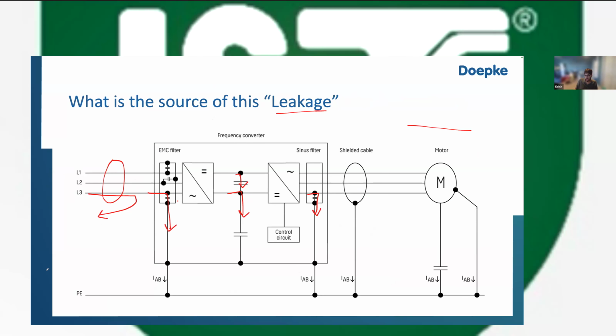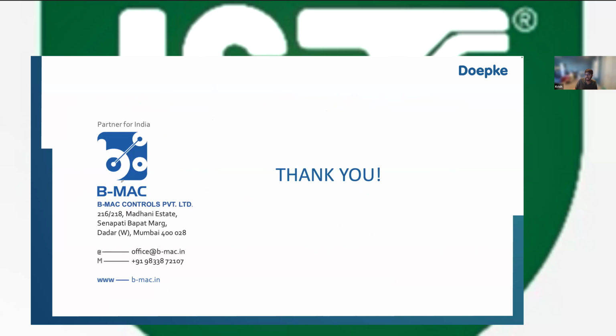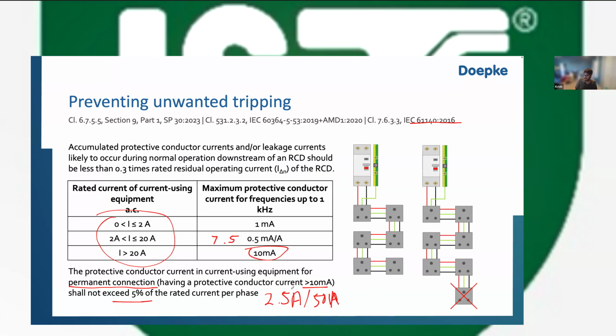And for that, I have to use a data sheet. I need to check the data sheet, or you need to hire a company to do a measurement. For example, BMAC, who is the partner for Doepke, can do this measurement for you, and then they can recommend a part for you. Just by knowing the rated kilowatt, I cannot recommend a particular thing, because I'm not familiar with this regenerative type, and I know that from manufacturer A to manufacturer B, the leakage current is wildly different. Remember, the manufacturers allow up to 5% of the rated current as leakage. So accordingly, you have to figure it out.